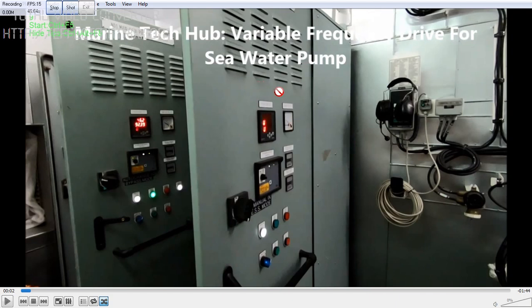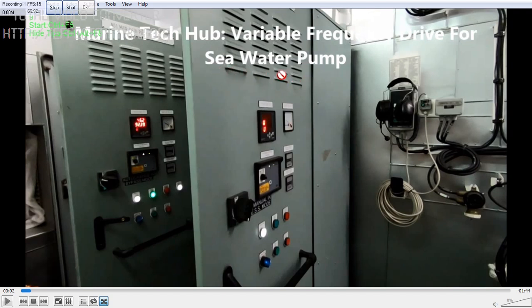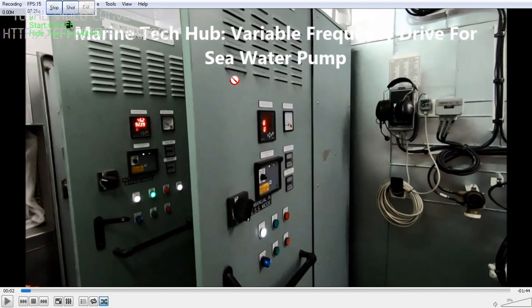In this picture we are describing about the Variable Frequency Drive used for the sea water pump. We use it to run at different RPM so that the temperature of the fresh water is controlled by running the sea water pump at different RPM. This is done by sensing the sea water temperature and the fresh water temperature required. We have a centralized cooling system on board the ship — the sea water pump will run and supply water to the central cooler.